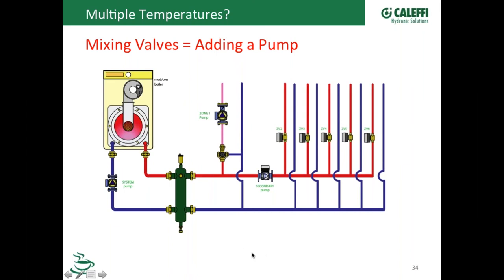So again, multiple temperatures. If you're adding a mixing valve, it doesn't matter if it's a thermostatic mixing valve or electronic mixing valve, you need to add a circulator. It's going to be the most important thing. I think he did an article years ago called A Little Floor Warming, Please, and he kind of tried to drill that into us, that you can't just put in, you would say, well, what if I put the mixing valve right here? It's on the discharge side of the pump. Won't it just go up like it?